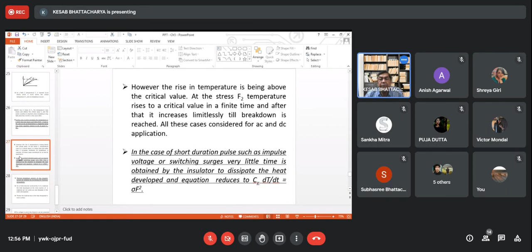Now, the thermal breakdown process of any insulator cannot be inhibited by increasing the thickness of the insulation. That is one very important point. For a finite thermal conductivity K of the material, the heat developed at the inner section of a material cannot come out and dissipate in the outer atmosphere. The thicker the material, the less heat is dissipated from the inner surface. Is this point clear?